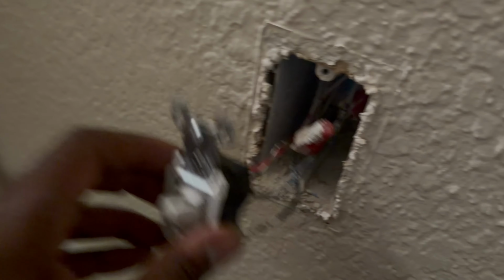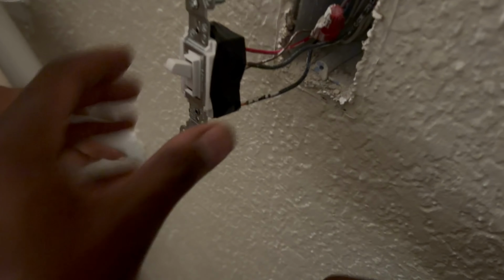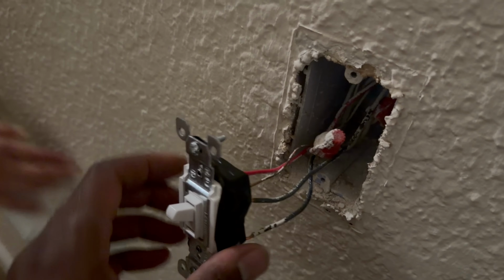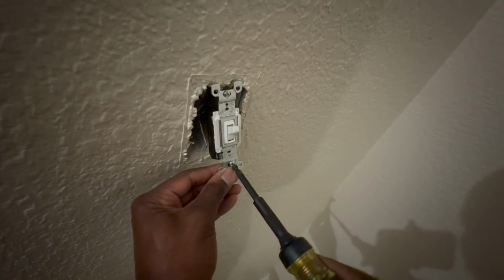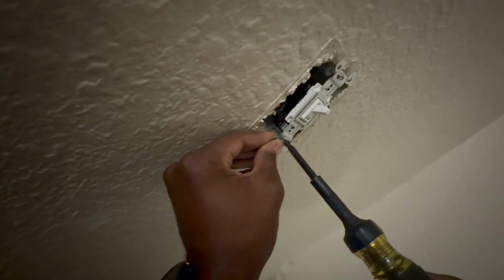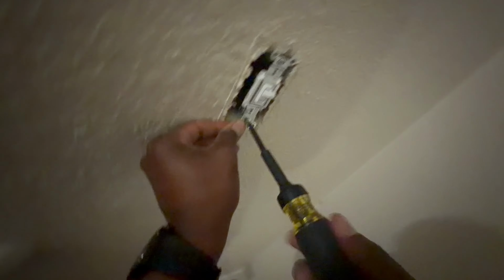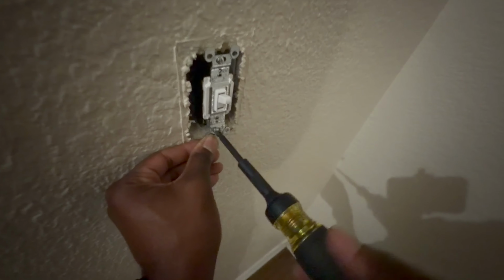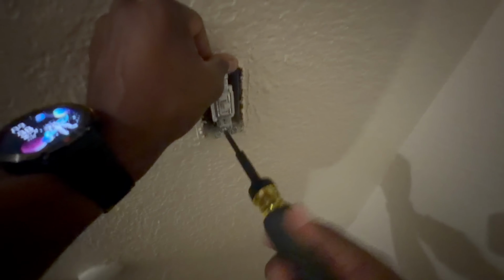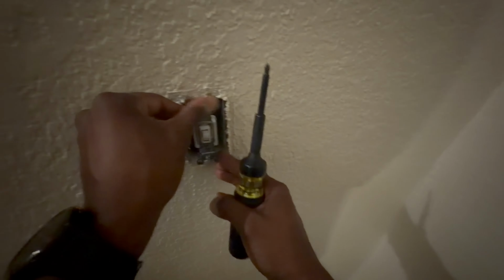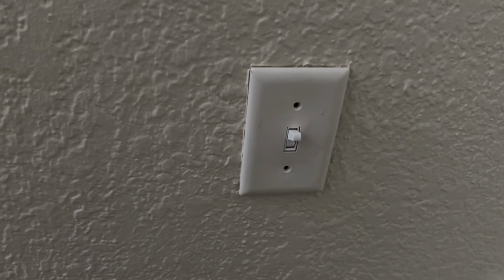You don't have to do this, you do whatever you want to, but this works for me. You can't see it once you put this into the wall, so this is something I like to do. Now this is just my preference. I do not tighten the screws all the way down. I like to get this device put in the box and then put the faceplate on to make sure it is square before I tighten the screws all the way down, because you cannot move the device easily when you have the screws all the way down.